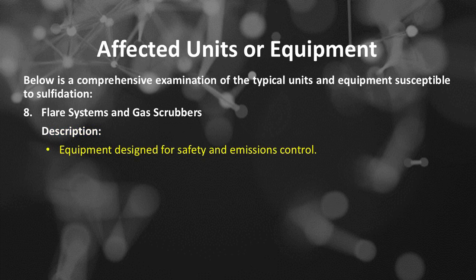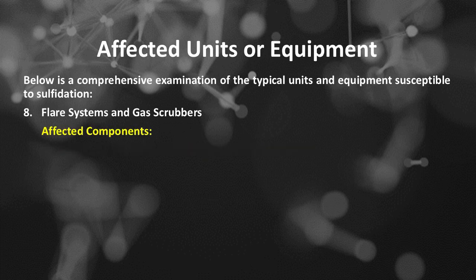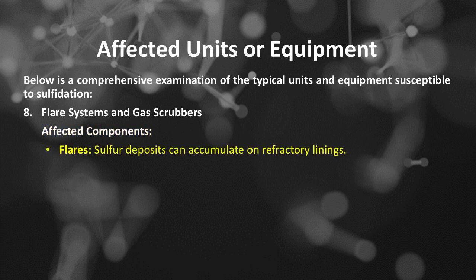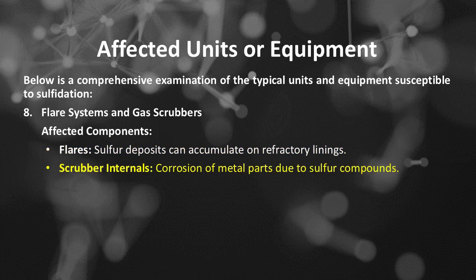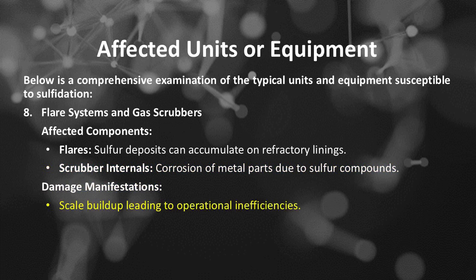Equipment designed for safety and emissions control. Flare systems and gas scrubbers affected components. Flares, sulfur deposits can accumulate on refractory linings. Scrubber internals, corrosion of metal parts due to sulfur compounds. Flare systems and gas scrubbers damage manifestations. Scale buildup leading to operational inefficiencies. Structural degradation and potential leaks.